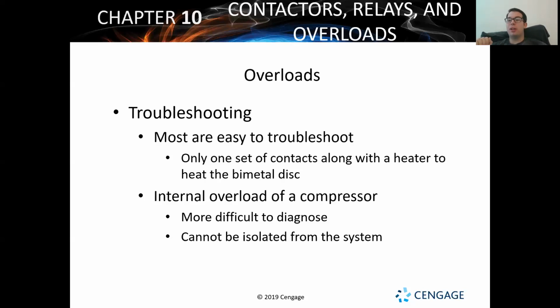Guy comes back to the office next week, and he's getting called into the boss's office because, hey, I'm being charged by the manufacturer for that compressor you put in. We have to pay for it. And you only budgeted for labor on your ticket. So what have I got to do? And the reason why the manufacturer's not going to pay for that compressor that you said had failed is because they got it back to their factory and they tested it and it hadn't failed. The system was working perfectly fine. You misdiagnosed internal overload. And I've seen that happen to guys.